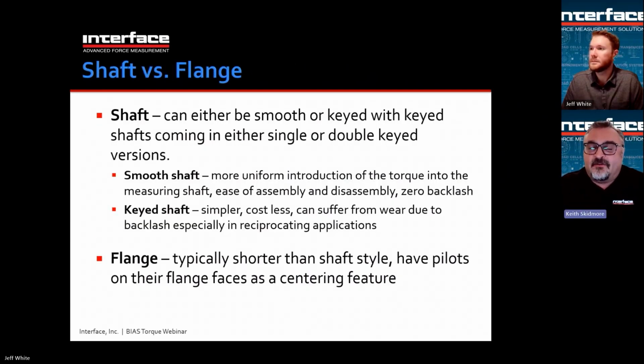So, shaft style versus flange style sensors. Shaft style sensors basically have a shaft that goes all the way through the sensor. It's one piece. That shaft has a section in the middle that has strain gauges adhered to it, and it might just be a straight through shaft, or it might have features machined into the shaft. A lot of times the shaft measuring element is much, much smaller than the shaft end. So sometimes customers see a big 32 millimeter shaft and think it's beefy and strong like a 32 millimeter shaft might be. But in reality, the center section may be quite a bit narrower. So that's just something to remember.